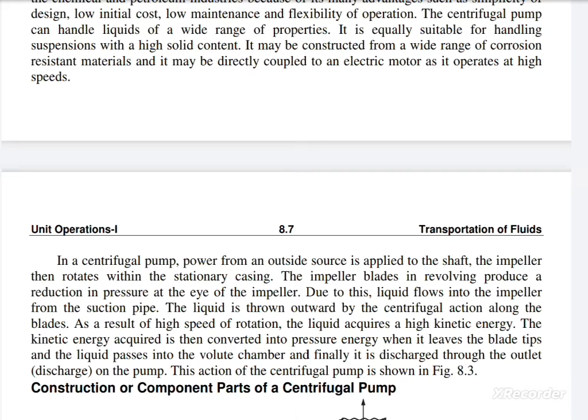In a centrifugal pump, power from an outside source is applied to the shaft. The impeller then rotates within the stationary casing. The impeller blades, while revolving, produce a reduction in pressure at the eye of the impeller. Due to this, liquid flows into the impeller from the suction pipe and is thrown outwards by centrifugal action around the blades.